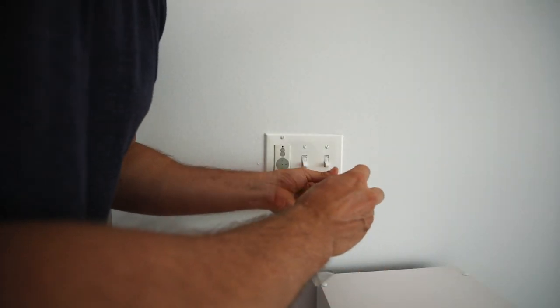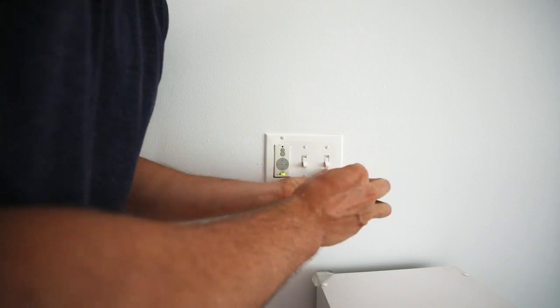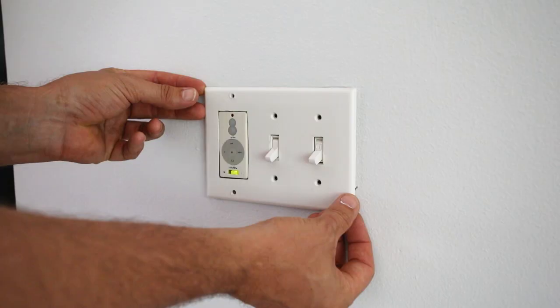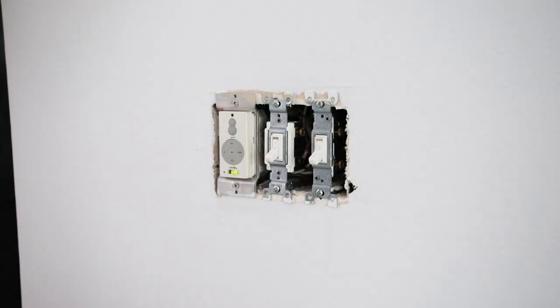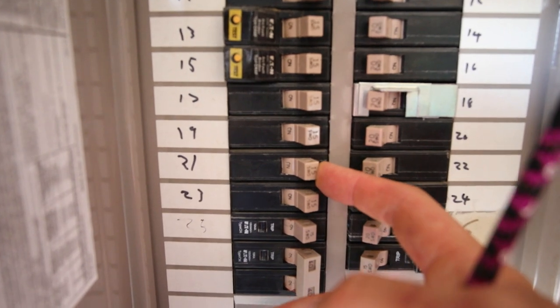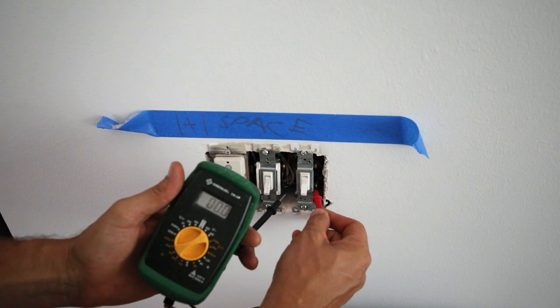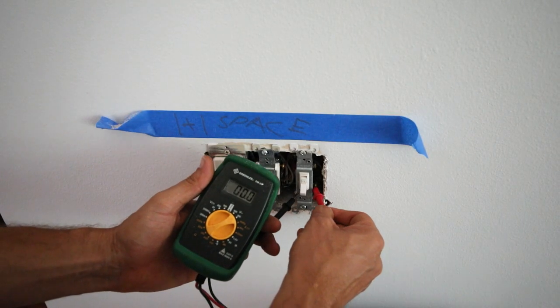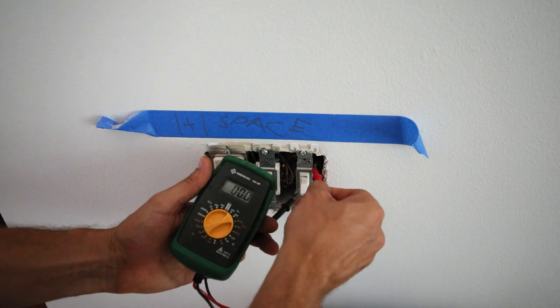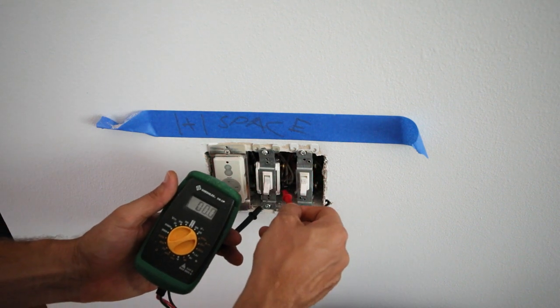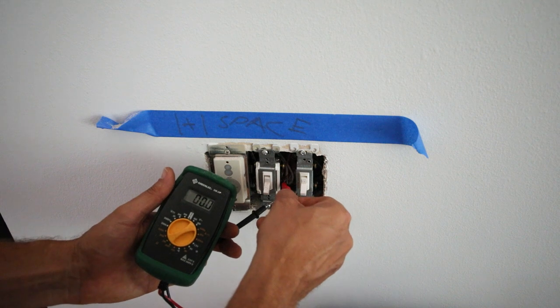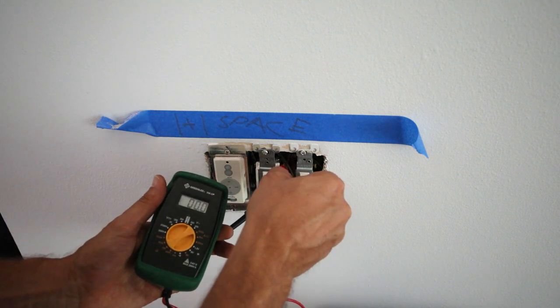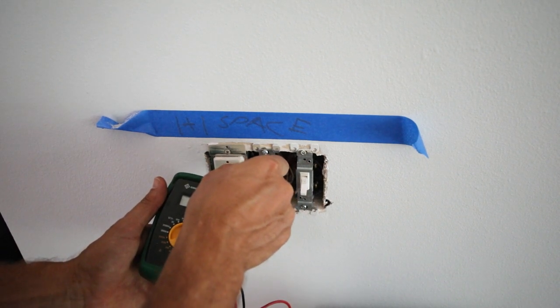So the goal here was to install the sconce above this set of switches. I'm going to take the cover plate off and see what I had to work with. Before I could do that, I had to kill the power to that light switch section. To confirm power wasn't there, I used a voltmeter and attached one leg to each screw and the other leg to a grounded piece of metal in the switch, made sure there was no power in any of those switches there.